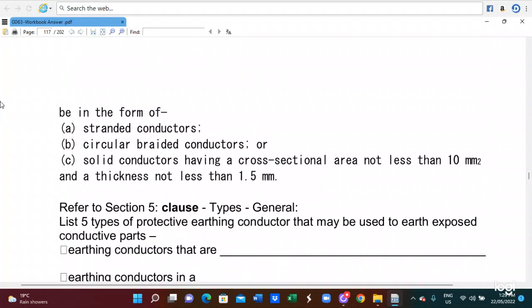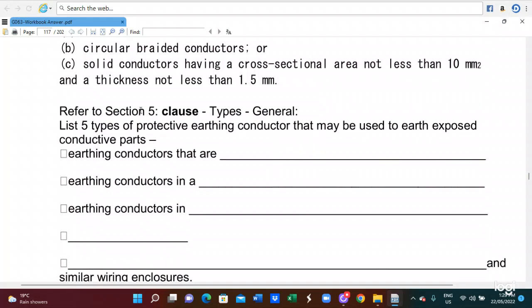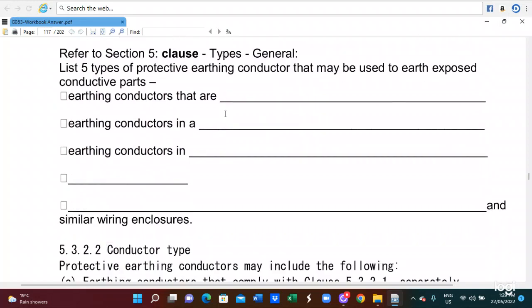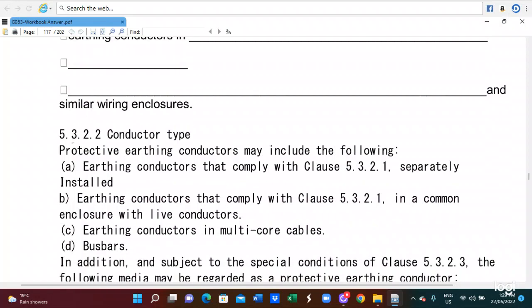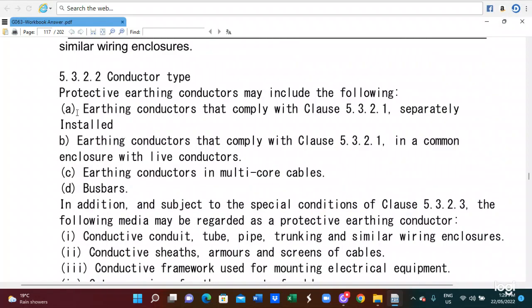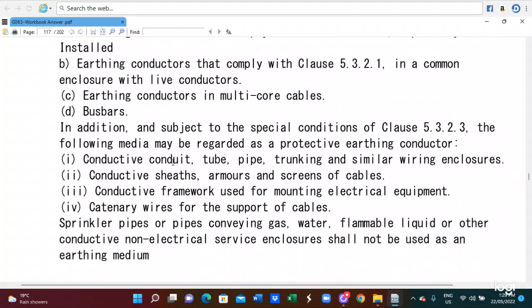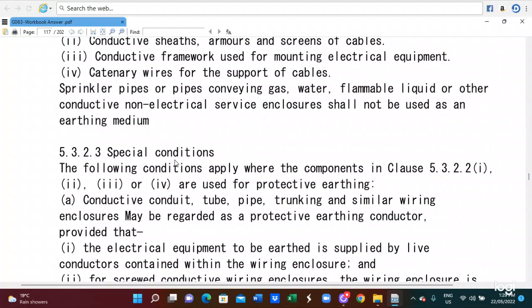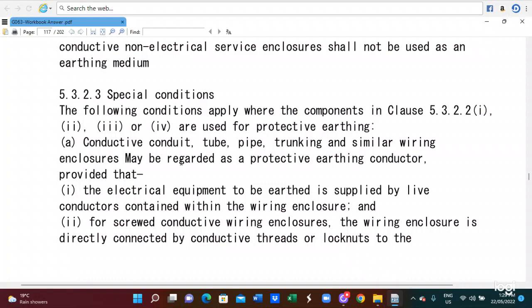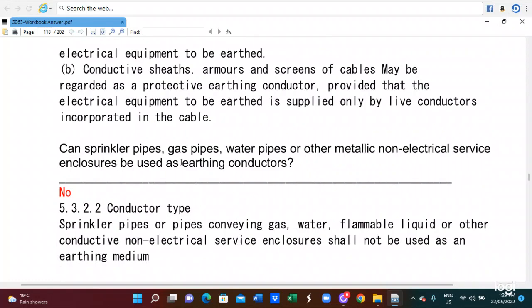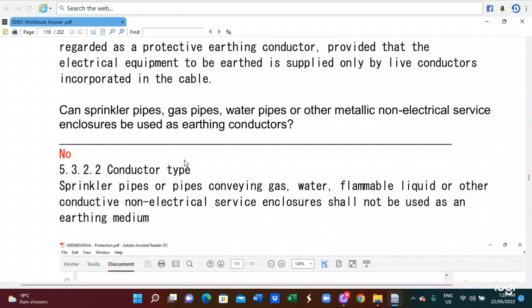or circular braided conductor, or a solid conductor having a cross-sectional area not less than 10 millimeter square, thickness not less than 1.5 millimeter. So you have to refer to section 5, earthing and general. So 5.3.2.2 is a conductor type. You can read from here, earthing conductor and also the bus bar. And 5.3.2.3 is a special condition you have to follow. And also 5.3.2.2 is conductor type.